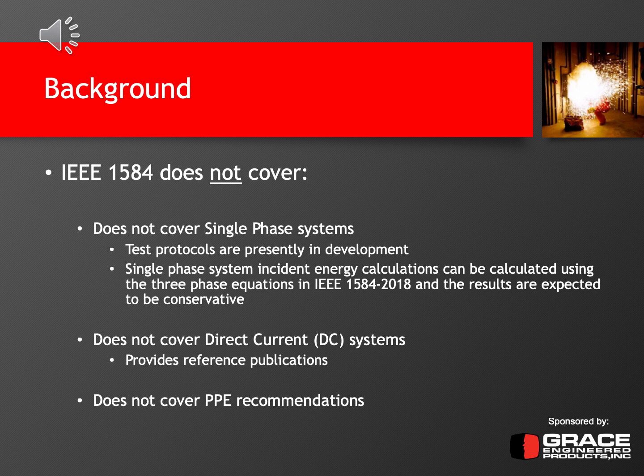1584 also does not cover direct current systems or DC systems, but it does provide a number of reference publications for anyone who's looking into doing a DC arc flash study. And it also does not provide personal protective equipment requirements or recommendations. You have to go to a different standard such as NFPA 70E to find those PPE recommendations based off of these incident energy calculations.